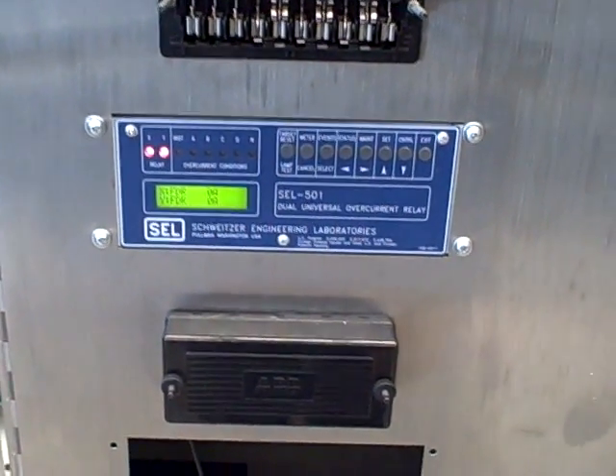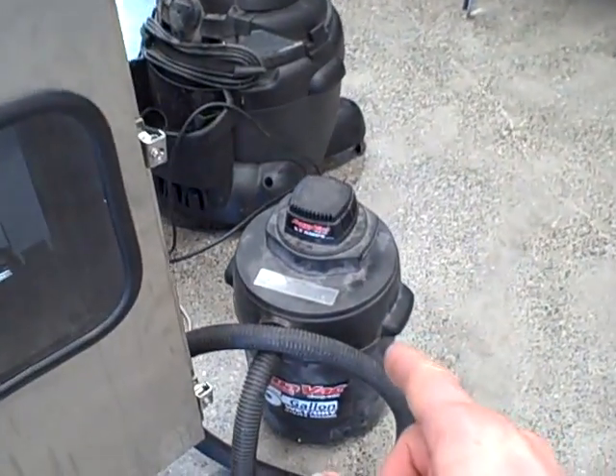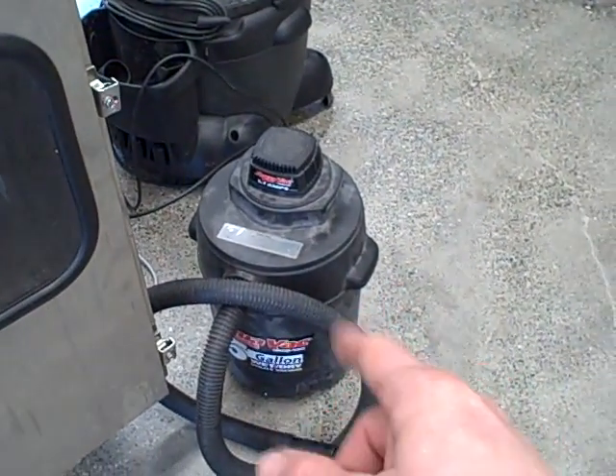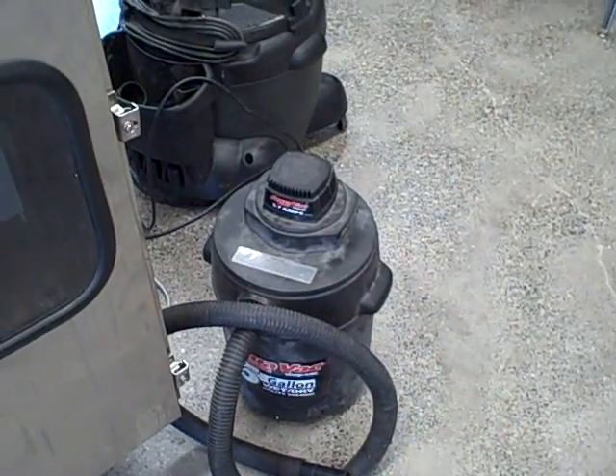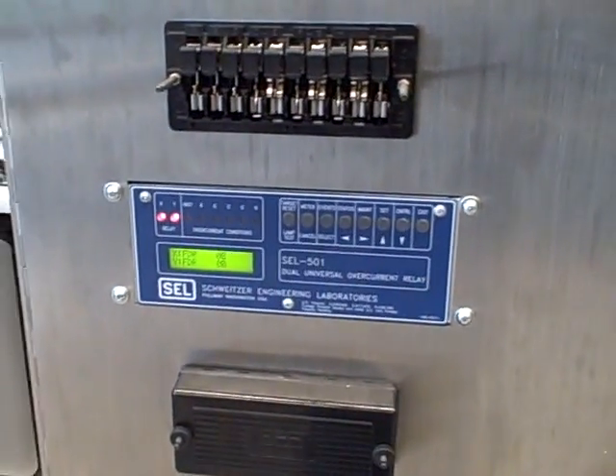Right now I have the settings set in such a way that the operating current from this vacuum cleaner will be sufficient to initiate a 51P trip. That's a time over current phase trip.